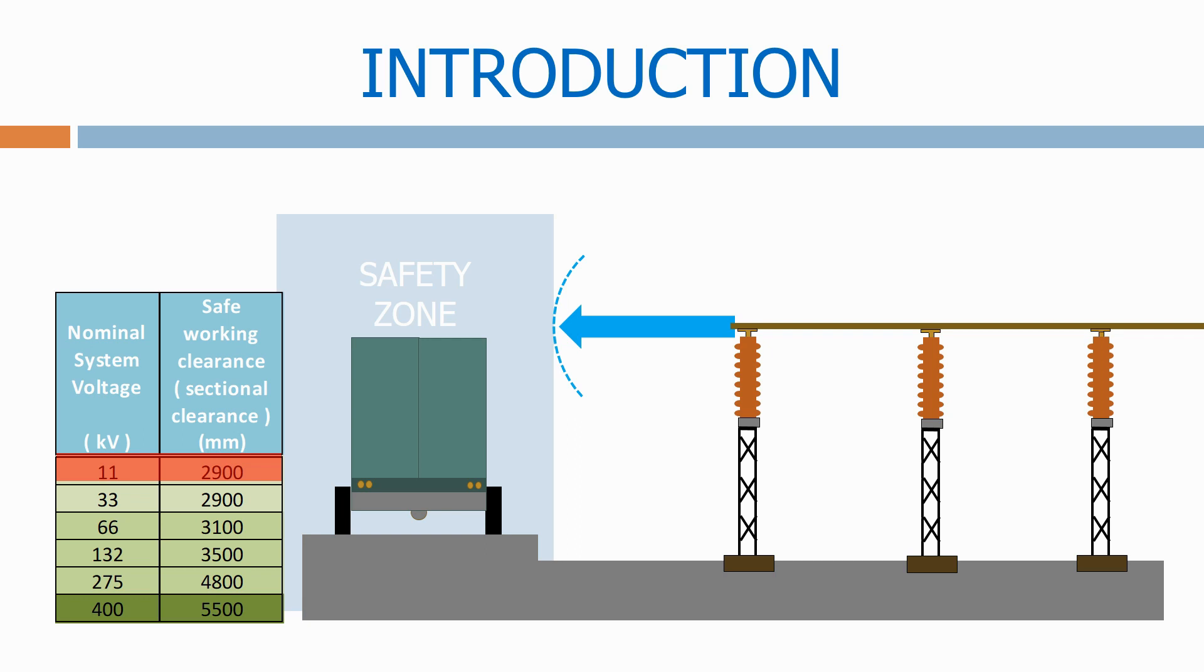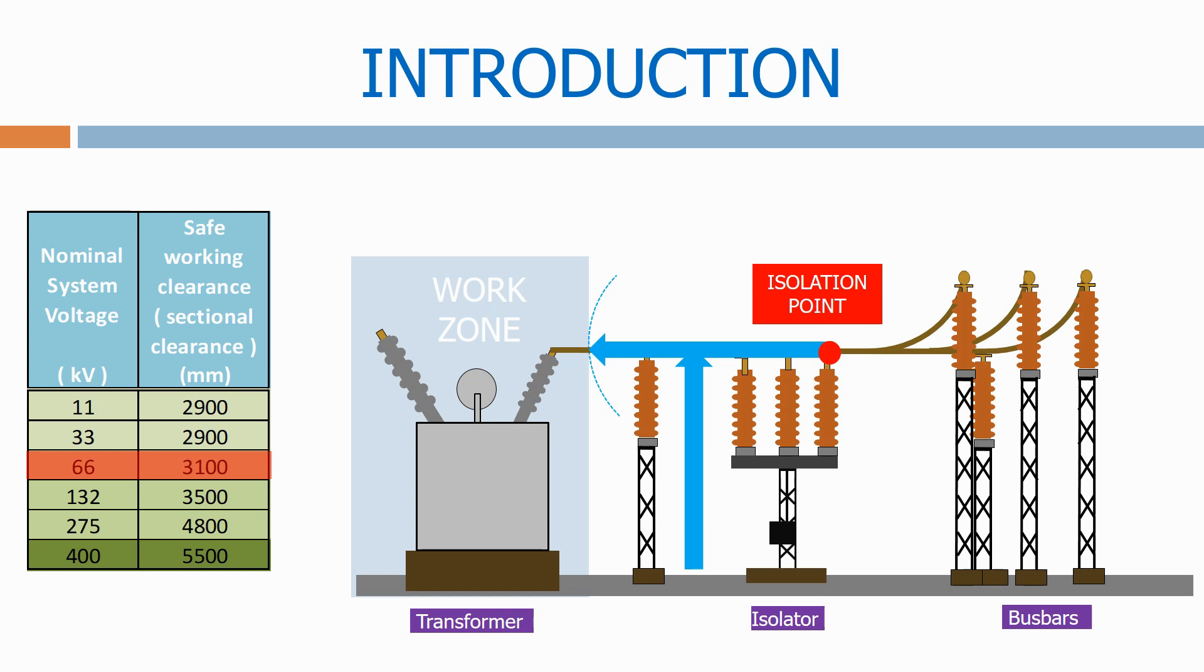In the final section we look at substation clearances. Air insulated substations use air as an insulating medium and we use the electrical clearances to lay out the equipment safely.